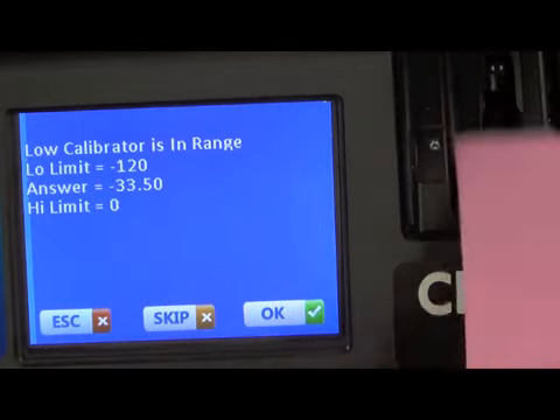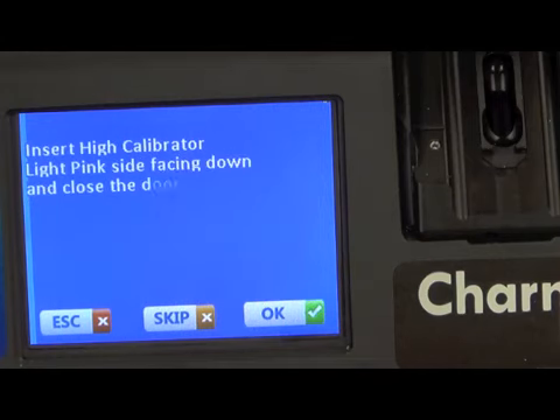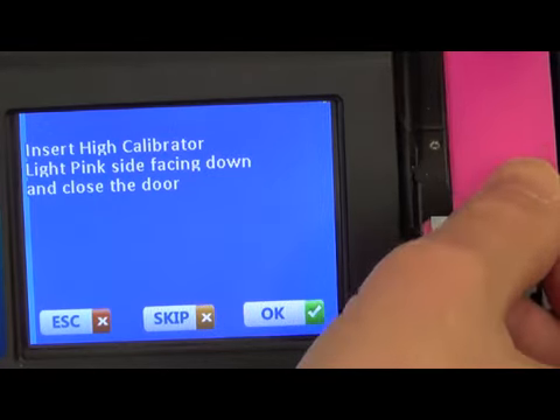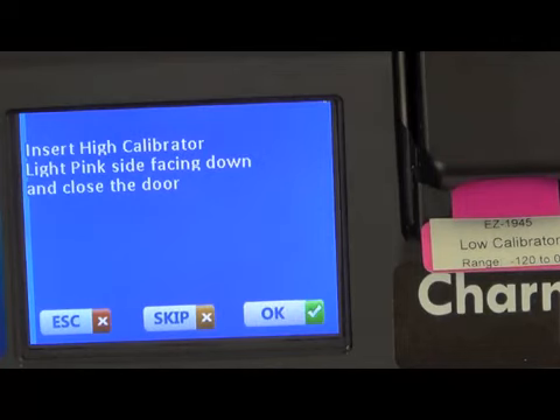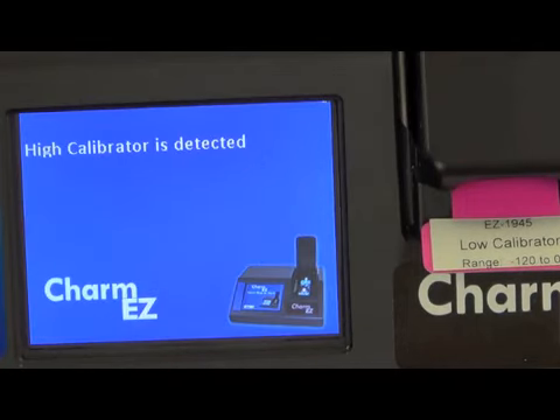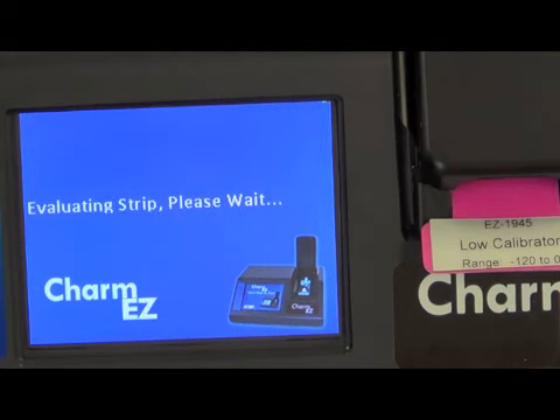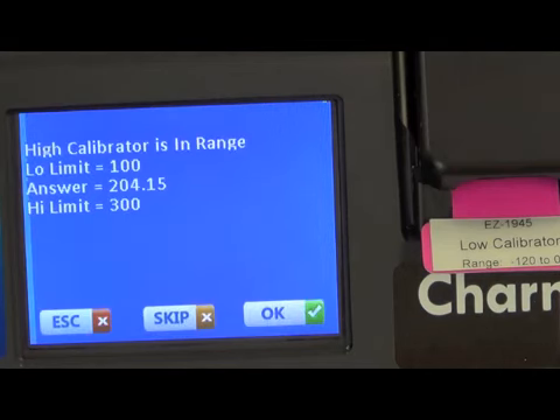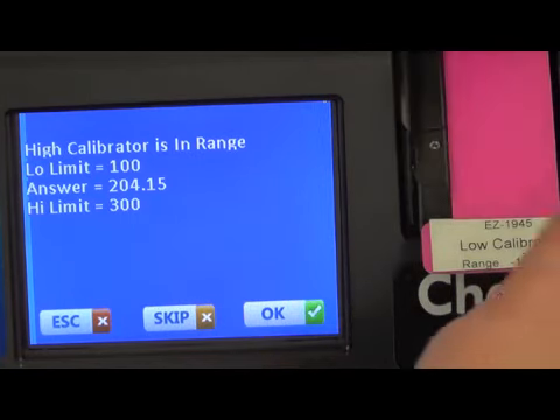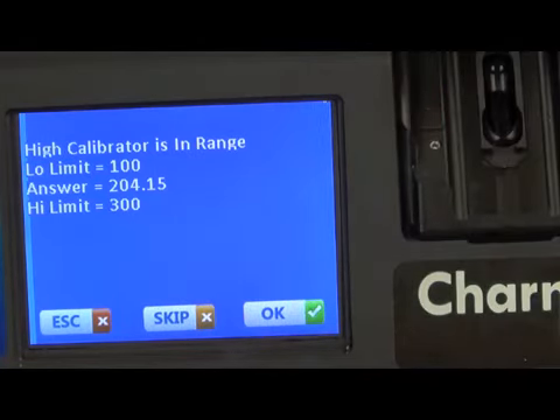Remove the strip, press OK, and the reader will prompt you to insert the high calibrator. Insert the light pink side of the calibration strip facing down. Close the door and press OK. Again, if the high calibration strip is in range, you will get an in-range reading with the appropriate values depicted on the screen. Remove the strip and hit OK.